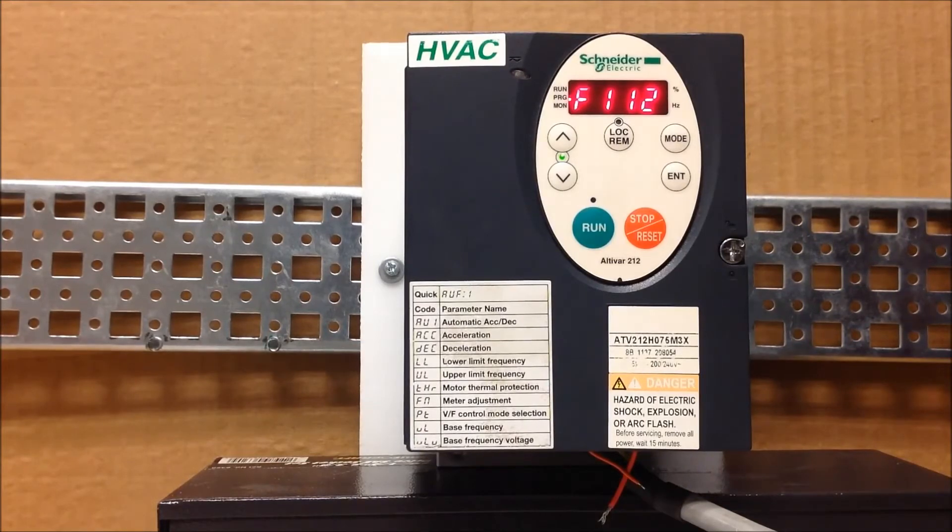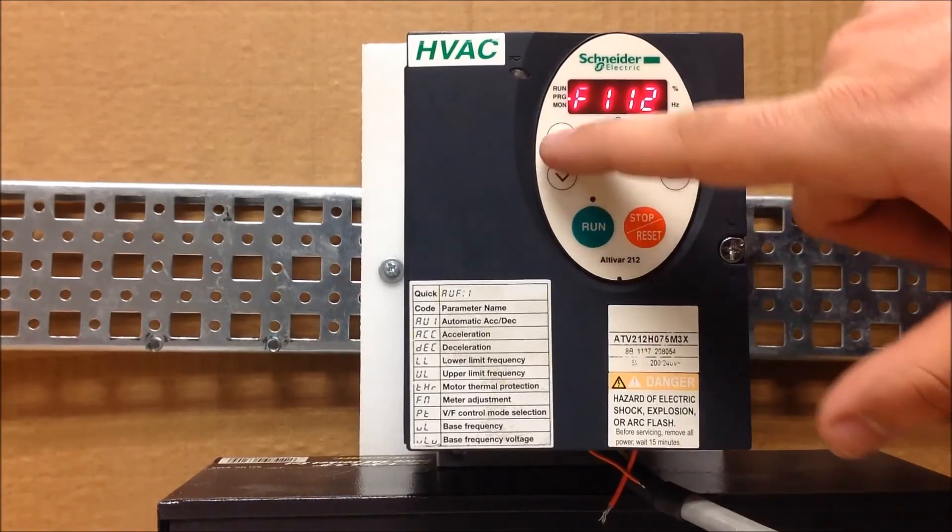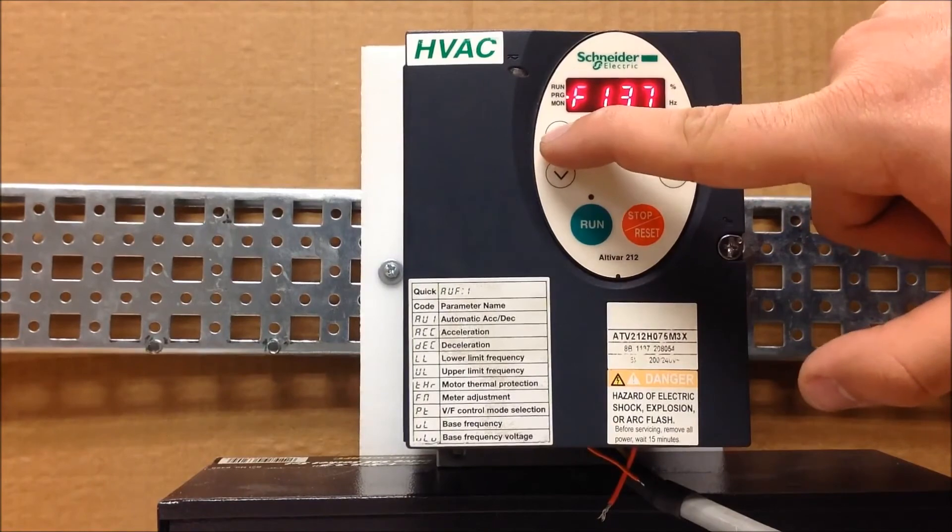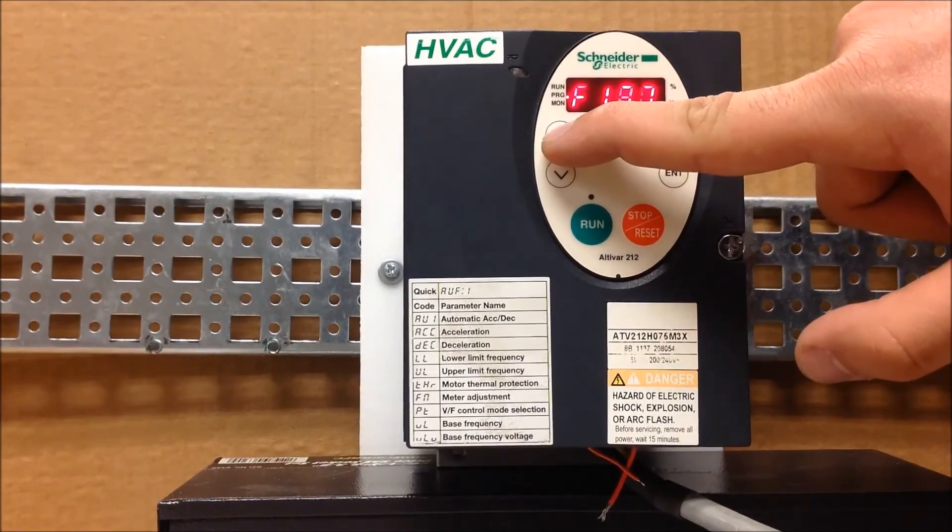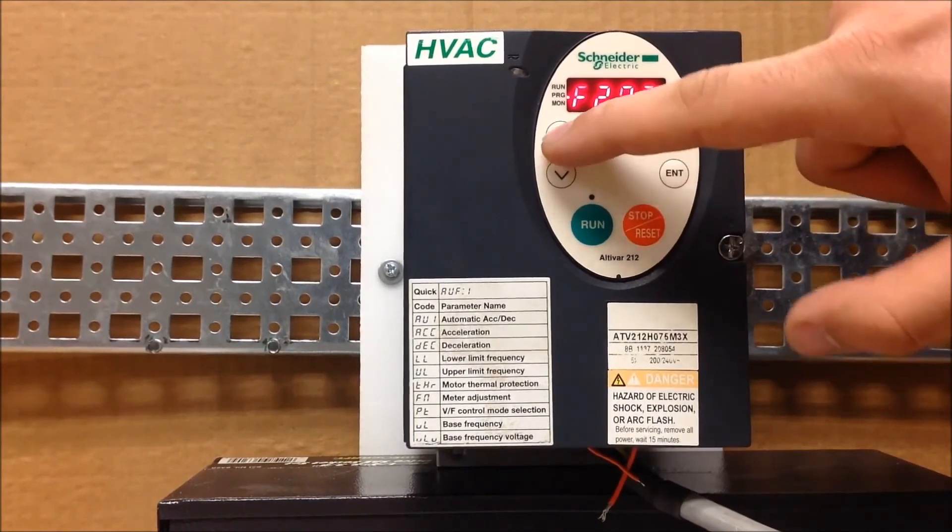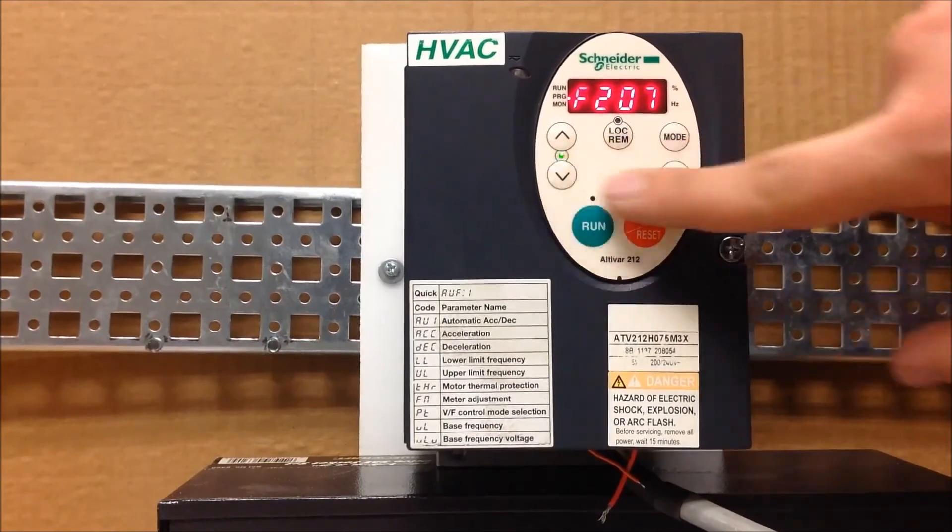So your first source right now is up and down. Let's go ahead and assume you want to use the VIA analog input value as your second speed source. To program that in, you have to go to F207, so 207 is your second speed source. Enter.